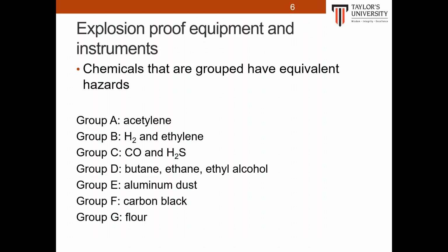The overall classification is only as good as the piece of equipment in an area with the lowest classification. Other than this, proper ventilation is also another method to prevent fires and explosions. The purpose of ventilation is to dilute the explosive vapors with air to prevent explosions and to confine the hazardous flammable mixture.